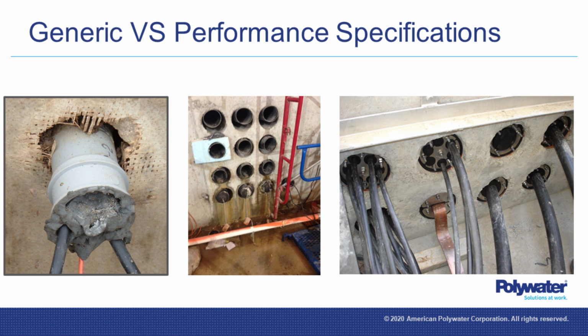But duck putty is made of clay, it dries, it sags, it doesn't hold waterhead pressure, there's no cable compatibility, there's absolutely nothing there. So if you're going to make a spec, you need to think about what you're trying to stop. What is the NEC code? What is the NESC code I could use? And how can we make it performance-based so that whatever is put into that conduit is compatible with all parts of the wire and will hold lots of waterhead pressure, like Polywater's chemical two-part foam that's closed cell, and our mechanical seals. Same thing goes for around the pipe, around the conduit. When it enters a concrete wall, typically people use mortar, but now you've got to wear special masks, it needs an accurate mixture of water, and it's got to be troweled in expertly, otherwise it's going to leak. Or they just go to the hardware store and get a cheap can of foam. Neither one holds waterhead pressure -- they weren't intended to seal around that. We make mechanical seals that do a much better job.